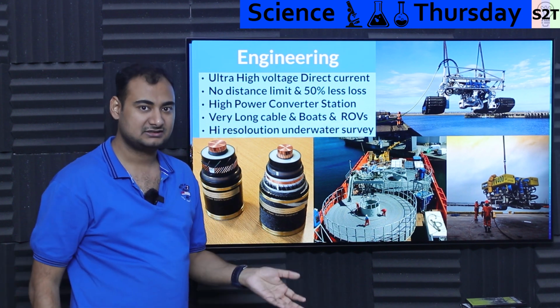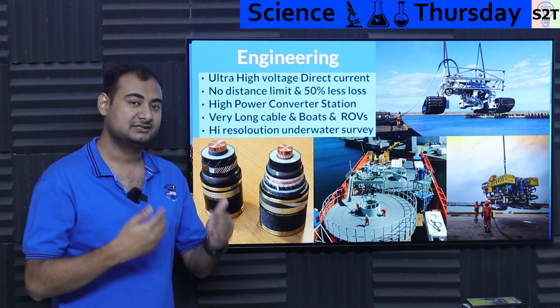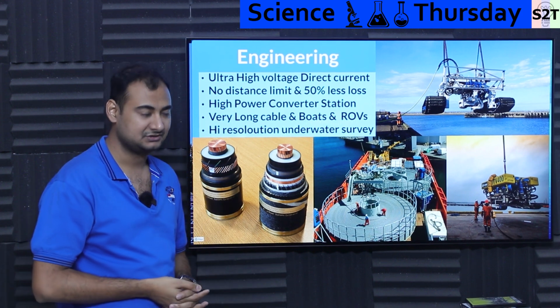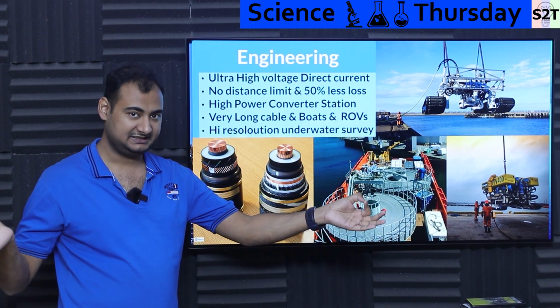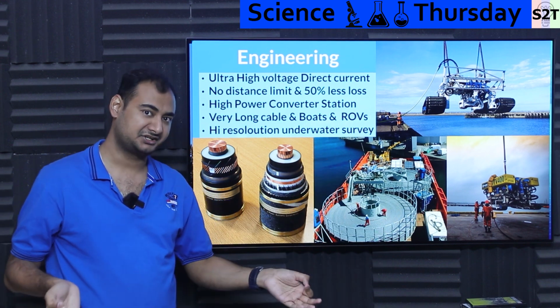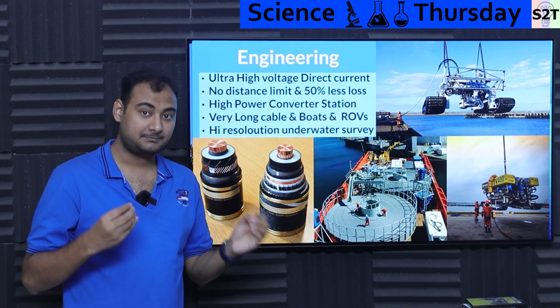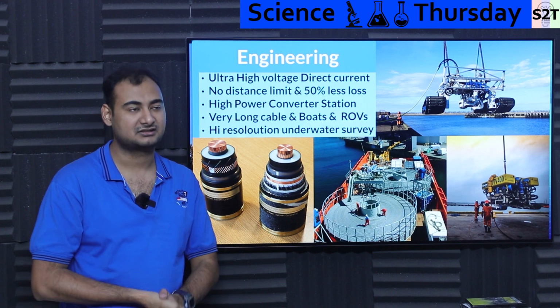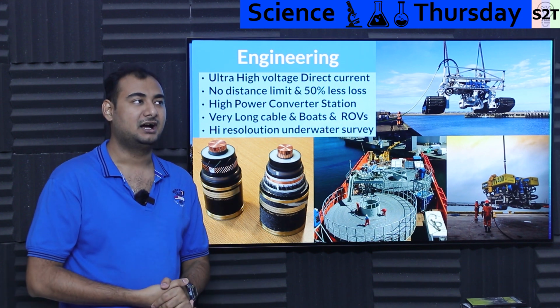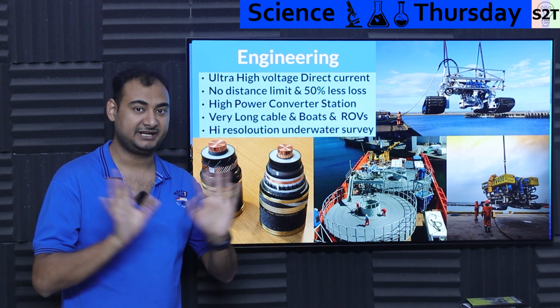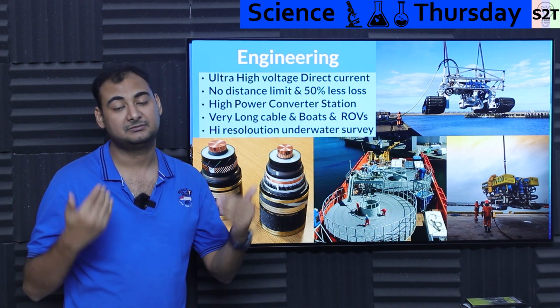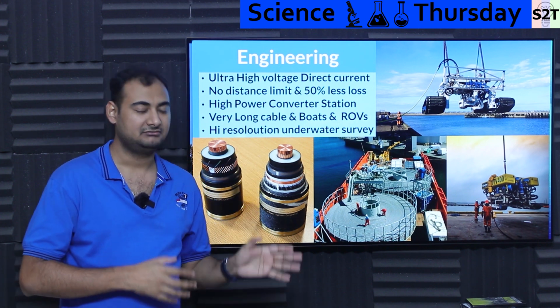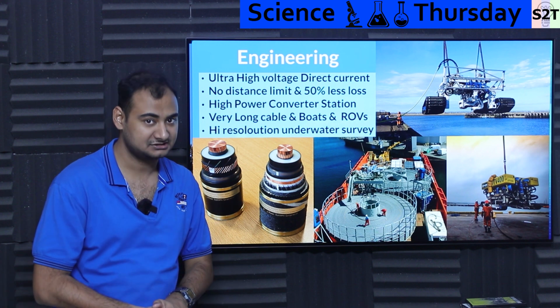DC also has losses, but much lower, and it does not have the physical range limitation. If you're making an AC cable that is 3000 kilometers long, the capacitance coupling from the environment to the conductor, because of the switching frequency, would be brutal. So all your energy, bye-bye. And that capacitive coupling is extremely brutal when buried under the sea.